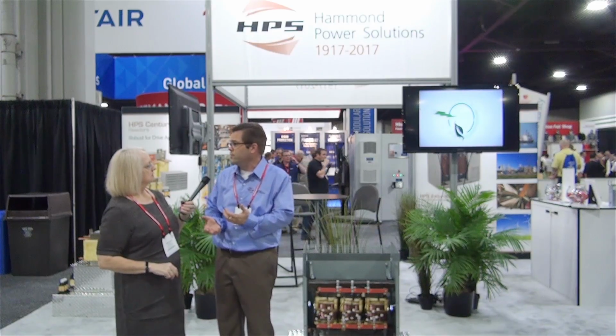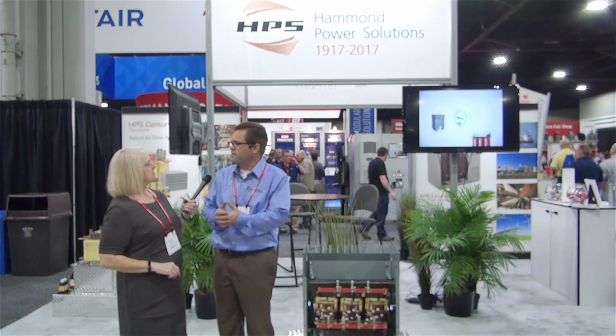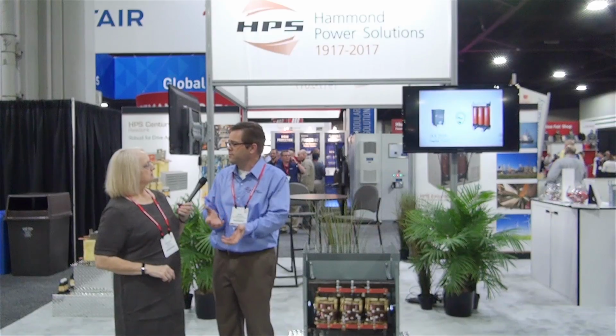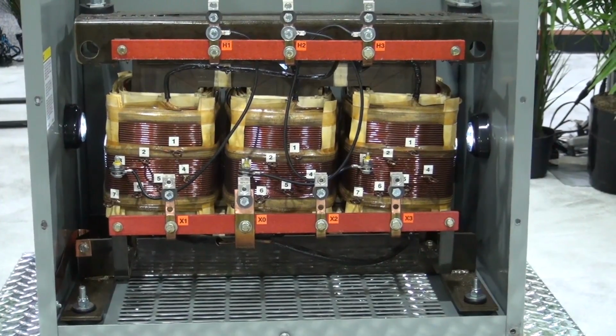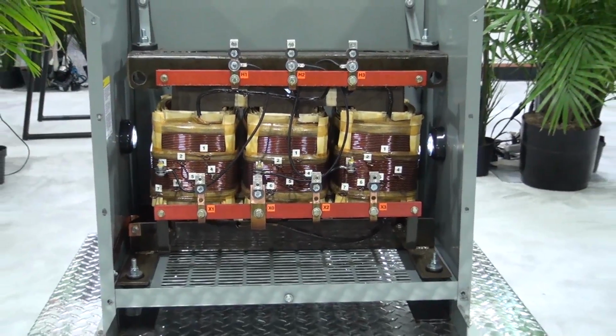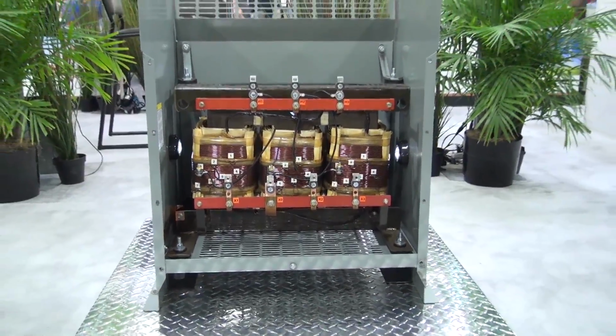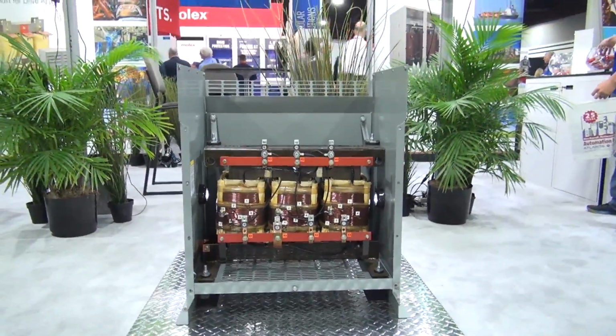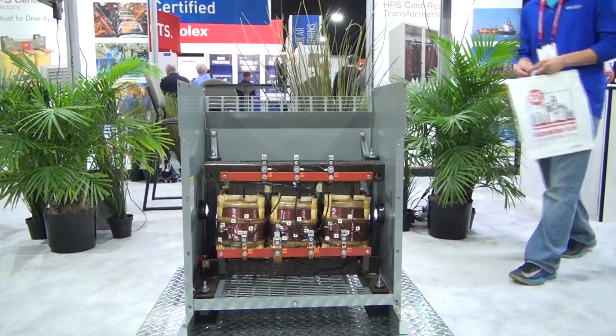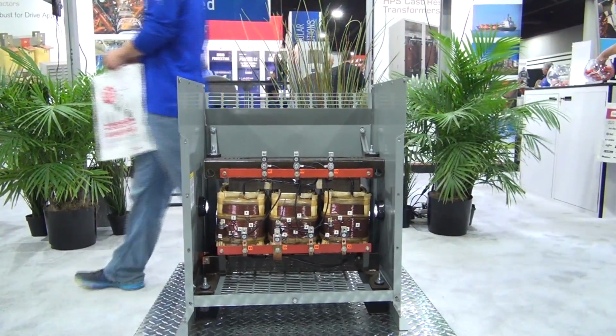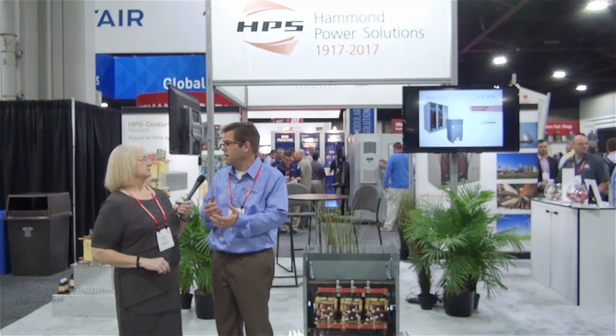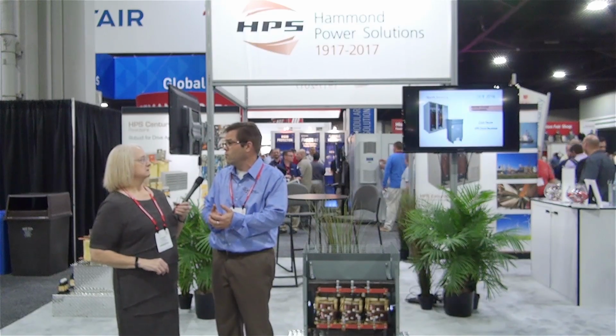We call it DOE 2016 because the Department of Energy, on January 1st of this year, updated all their efficiency levels for both low voltage and medium voltage, which required a redesign of the transformers to meet these new standards. They were really aggressive standards—efficiency levels were increased by 25 to 30% on most of those units.